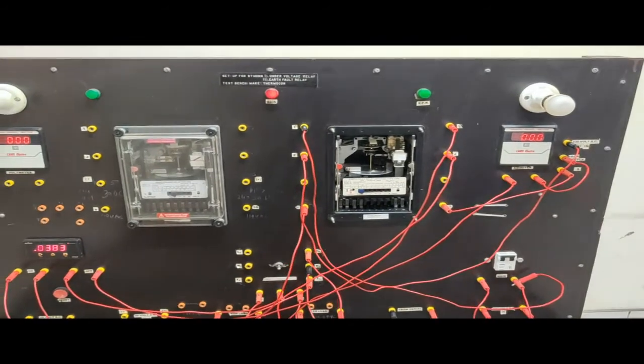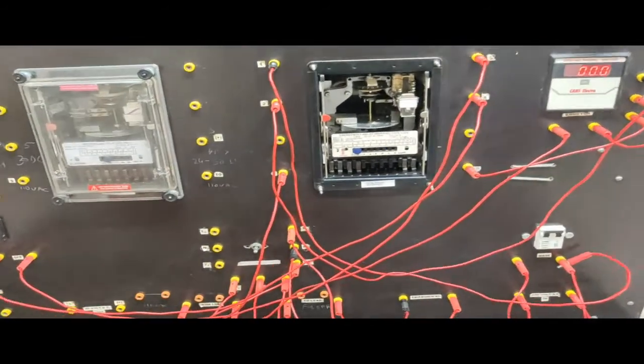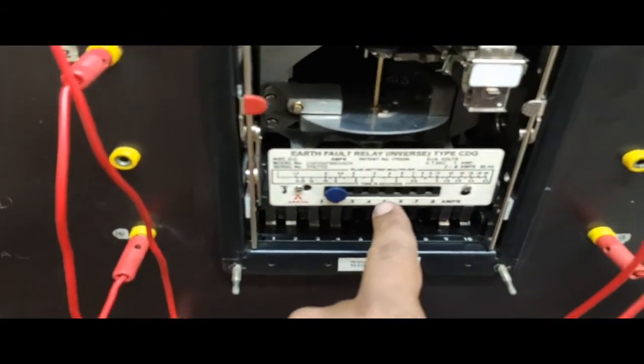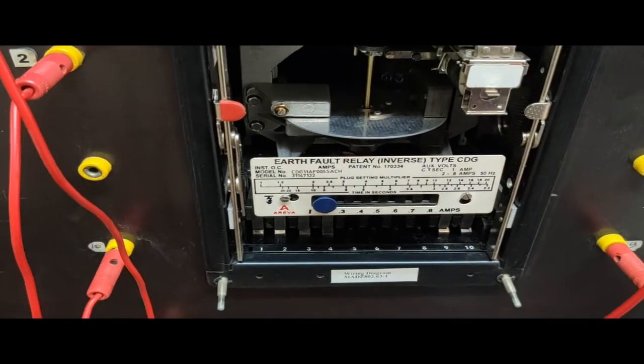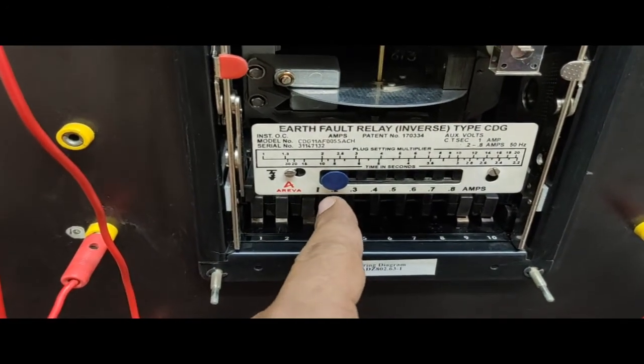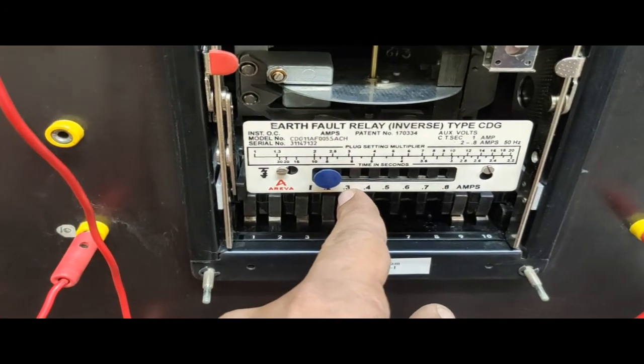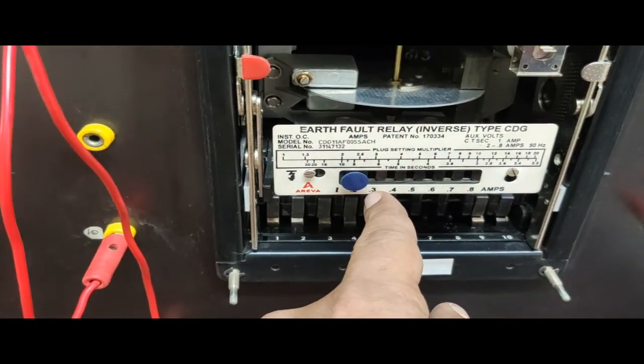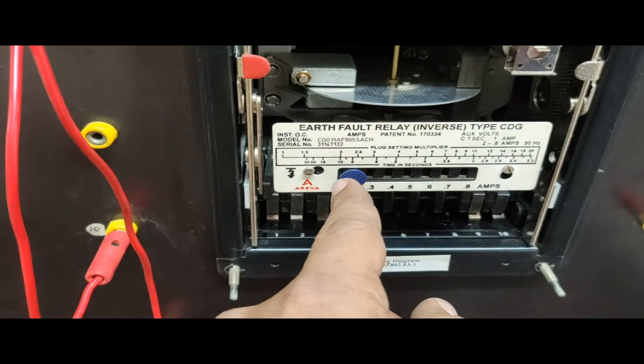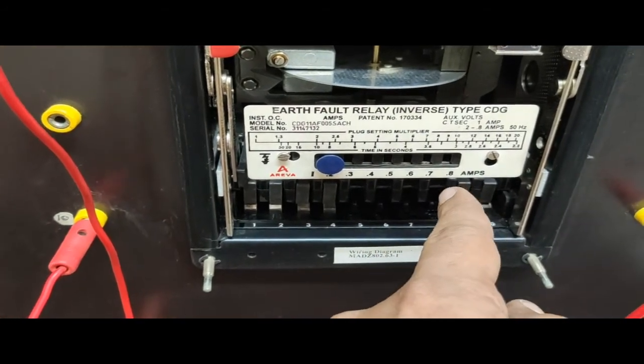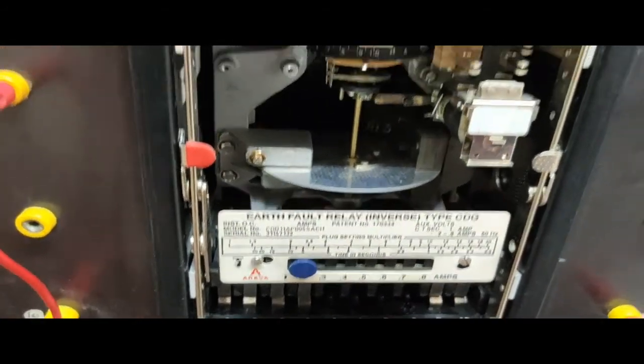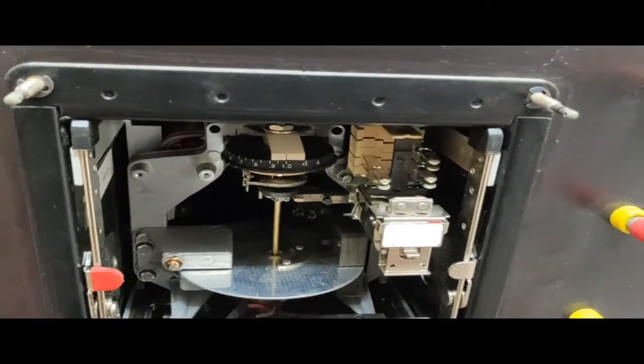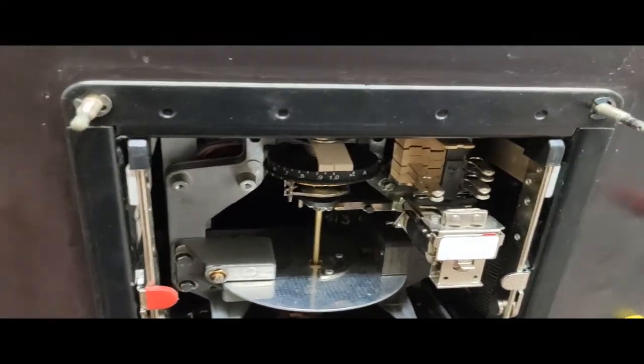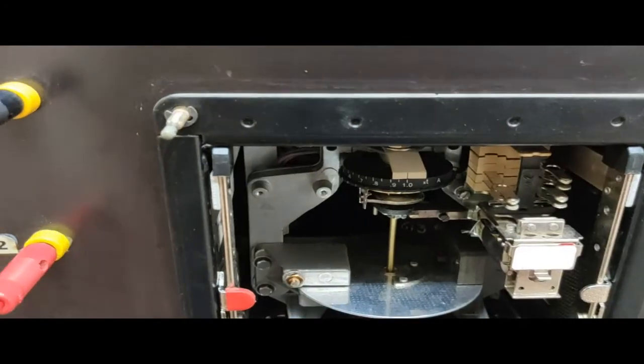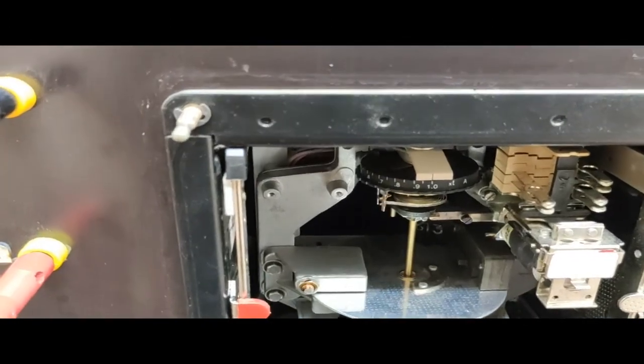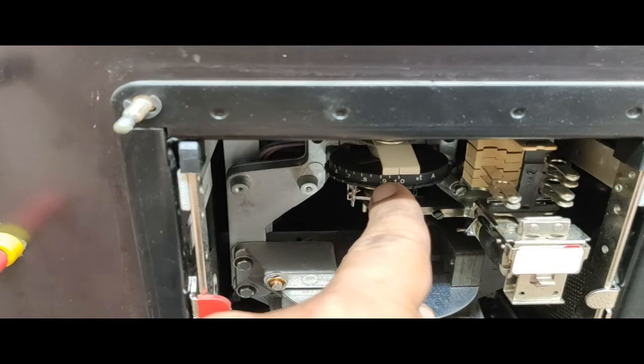Now come to another interesting feature. As I mentioned, this plug setting is required to change the operating current of the relay. That means now the relay will operate at 0.2. If I put the plunger in that particular hole, then it will operate at 0.3. So the same relay can be operated from 0.2 to 0.8 according to the requirement of the user. Another thing is how to control the relay operating time. The relay operating time can be set using this dial. This is called the time multiplier setting. So now the time multiplier setting is fixed at 1.0.